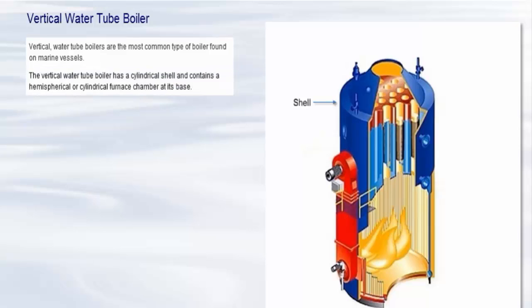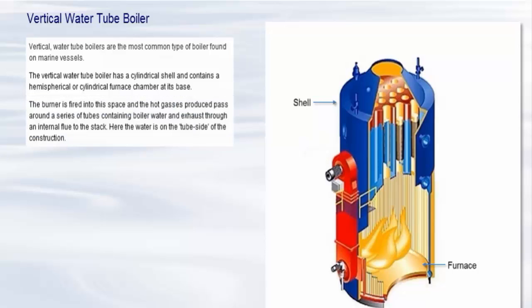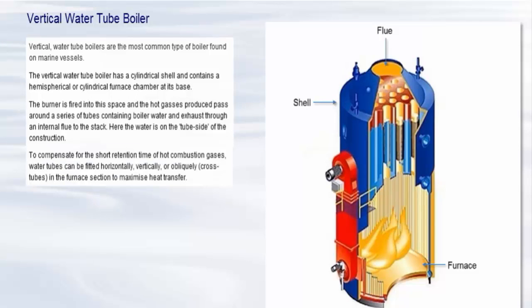The vertical water tube boiler has a cylindrical shell and contains a hemispherical or cylindrical furnace chamber at its base. The burner is fired into this space and the hot gases produced pass around a series of tubes containing boiler water and exhaust through an internal flue to the stack. Here the water is on the tube side of the construction. To compensate for the short retention time of hot combustion gases, water tubes can be fitted horizontally, vertically or obliquely cross tubes in the furnace section to maximize heat transfer.